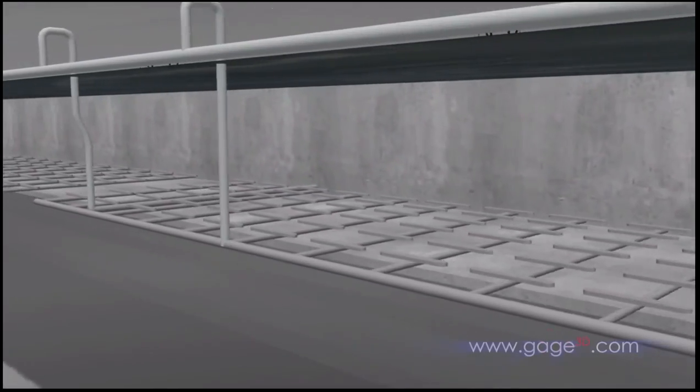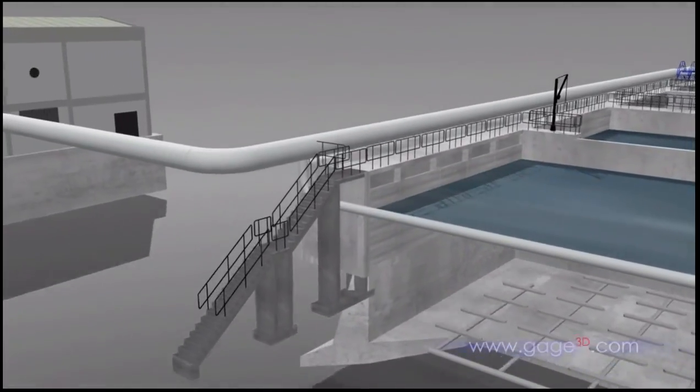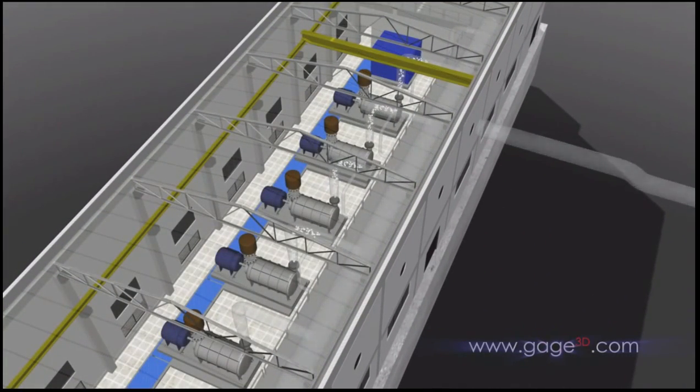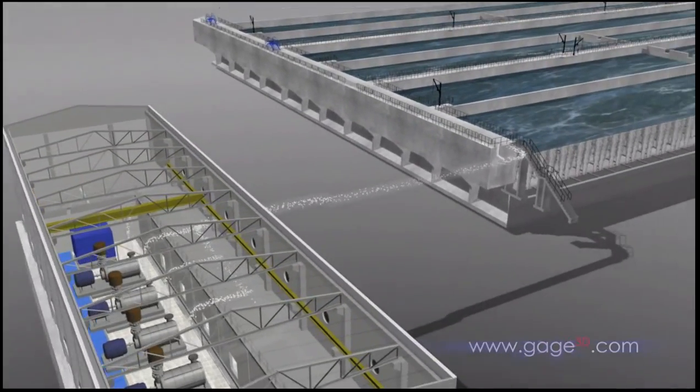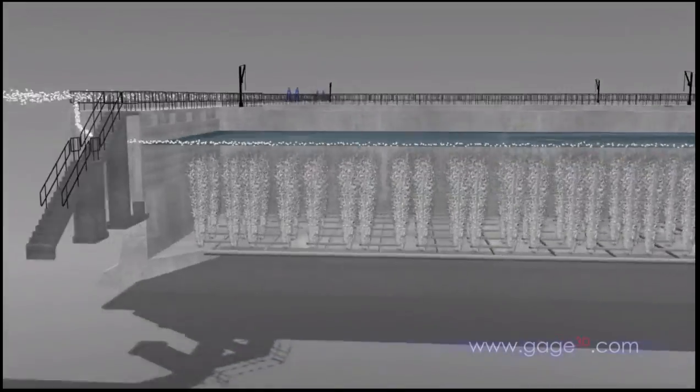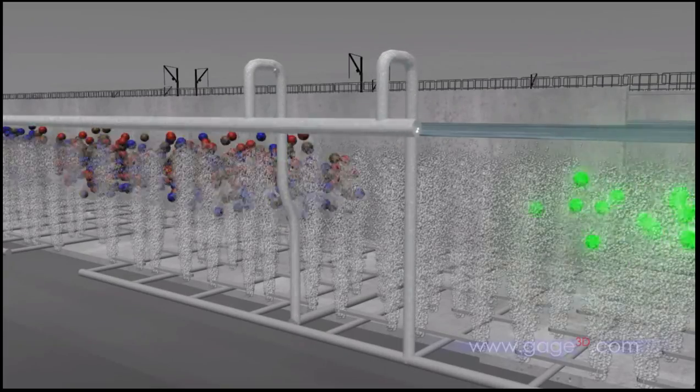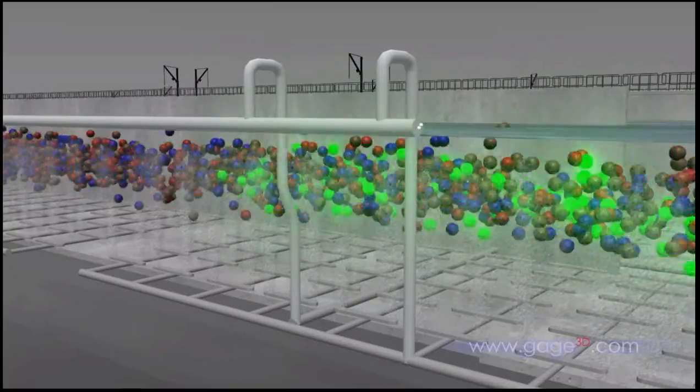The first secondary treatment stop is the aeration basin. Unlike primary treatment, this part of the treatment process relies on biological action rather than physical separation. Blowers generate oxygen that is distributed through a network of pipes into the aeration basin. The oxygen generated by the blowers is used by hungry bacteria, as shown in green. They feed on the solids, reducing their volume and removing nutrients.